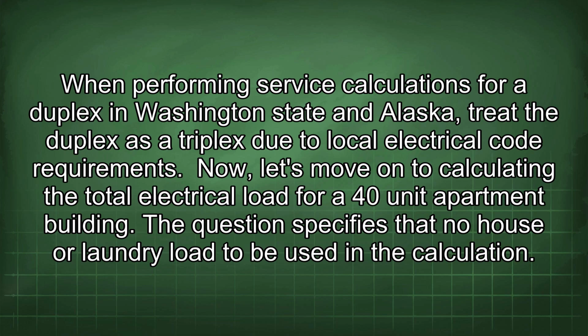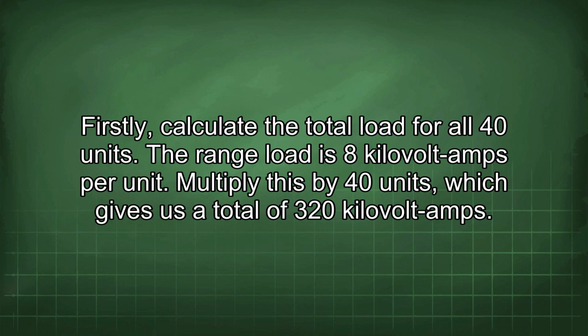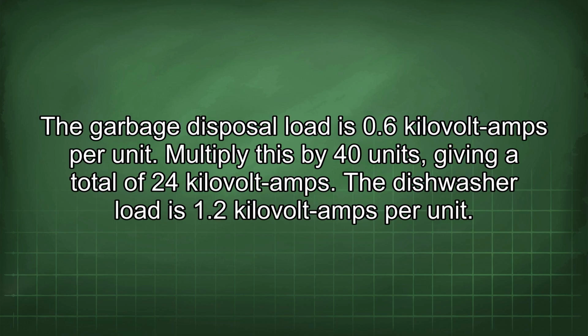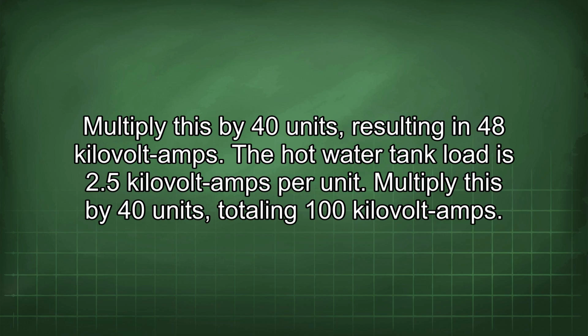The question specifies that no house or laundry load is to be used in the calculation. Firstly, calculate the total load for all 40 units. The range load is 8 kVA per unit. Multiply this by 40 units, which gives us a total of 320 kVA. The garbage disposal load is 0.6 kVA per unit. Multiply this by 40 units, giving a total of 24 kVA. The dishwasher load is 1.2 kVA per unit. Multiply this by 40 units, resulting in 48 kVA.